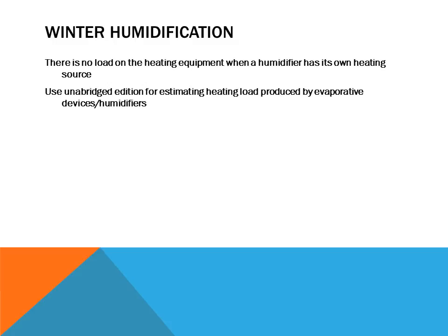A couple of things we also have to look at when we're looking at latent loads is the humidification that we actually have to add to the house in the winter time. And of these loads, of course, the higher the humidity, it will help with the heat load, but not going too high, because it can cause damage to the structure through condensation forming on windows and dripping, or having moisture get trapped into drywalls and cold areas and causing mold to grow. But controlling the humidity is very important year-round, even in the summertime.